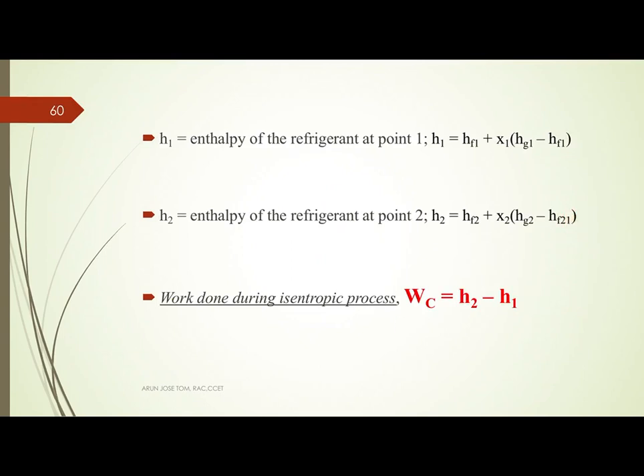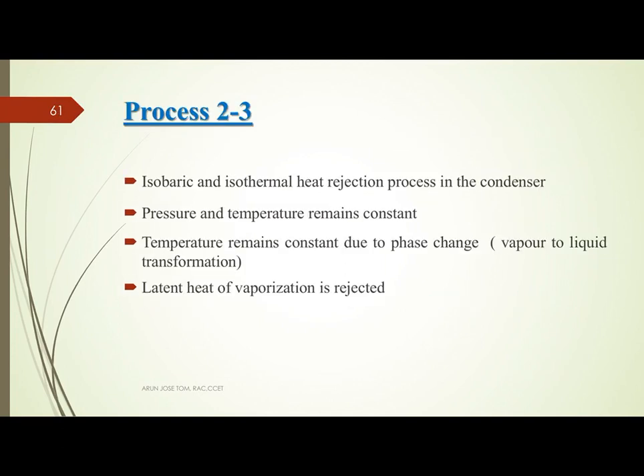The work done during the compression process is H2 minus H1. The next process is process 2 to 3 — isobaric and isothermal heat rejection. In process 2 to 3, the process is condensation. Here, we reject the latent heat of vaporization from the refrigerant, and the refrigerant condition changes from point 2, that is wet vapor, to point 3, that is saturated liquid.